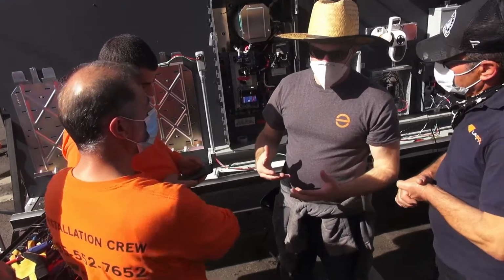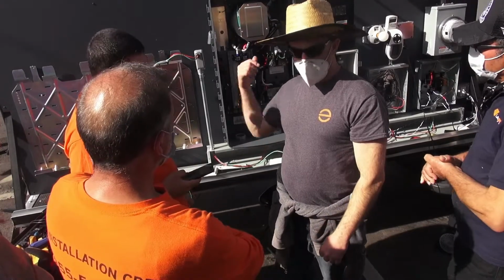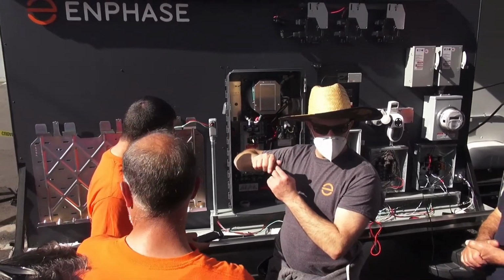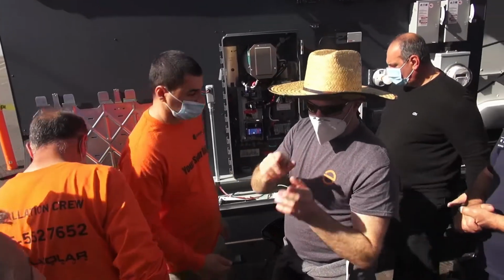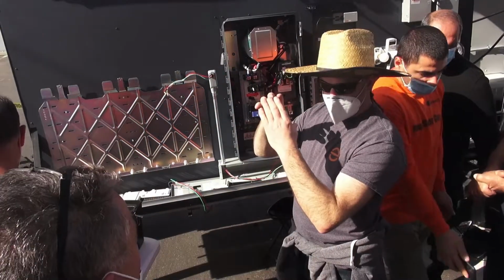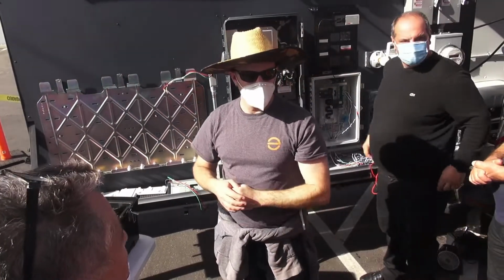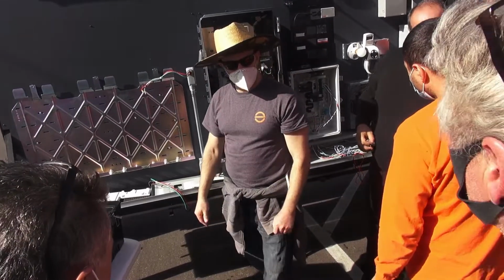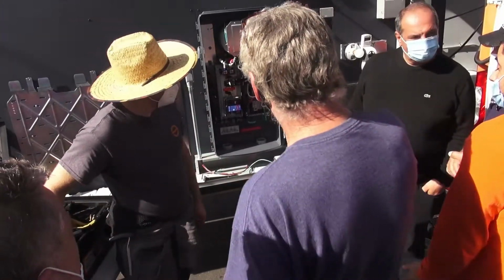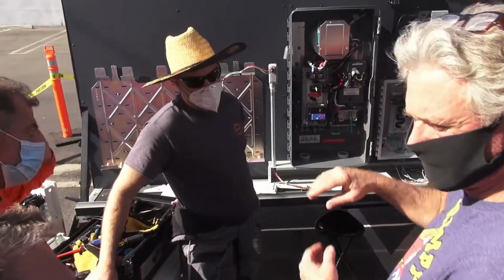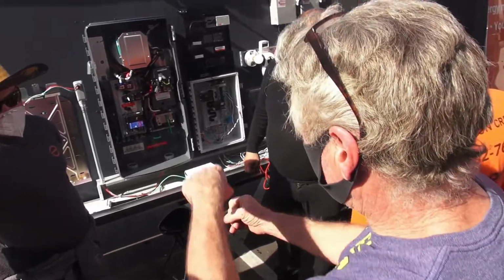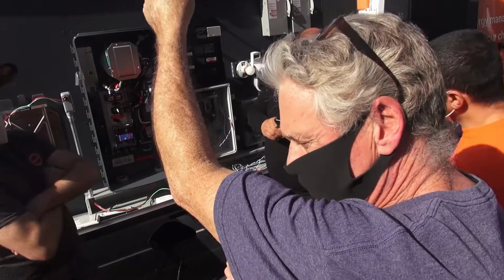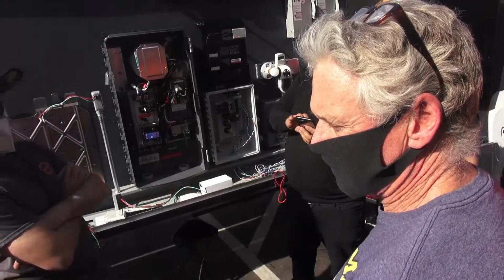The other question is, some inspectors will say, "Oh, that's not a combined junction box. It's a battery. Don't do your splicing there." So what you just said would absolutely work: just a small multi-purpose box, an actual junction box. That would definitely work. Good that you pointed that out, because that's a common mistake in any kind of sub panel. Wire nuts, pulling wires in, wire nuts, pulling wires out. You just used a sub panel as a junction box. You're not allowed to do that.